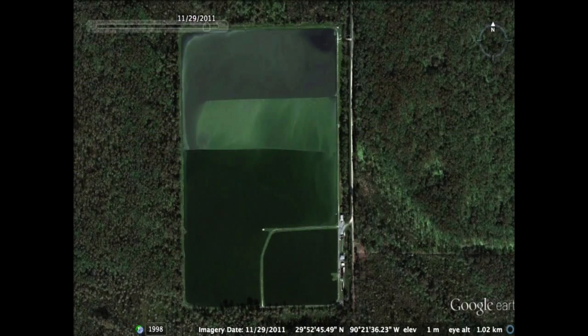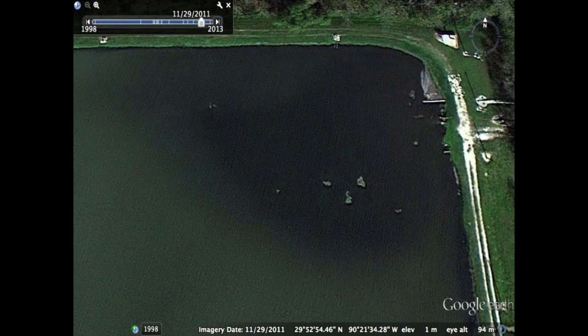This 60-acre wastewater lagoon used a single lagoon aerator to degrade a number of sludge islands that had formed at the inlet of 4 towns' wastewater to the lagoon system. Because the lagoon aerator is only moving water along the bottom of the lagoon, the constant water movement at the sludge level will erode the base of the islands and collapse them. Then, the sludge makeup of the islands is distributed evenly along the bottom and activated.